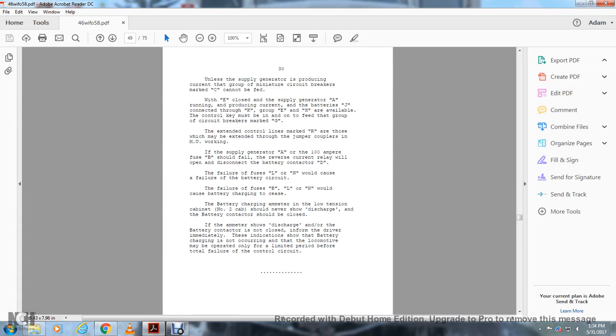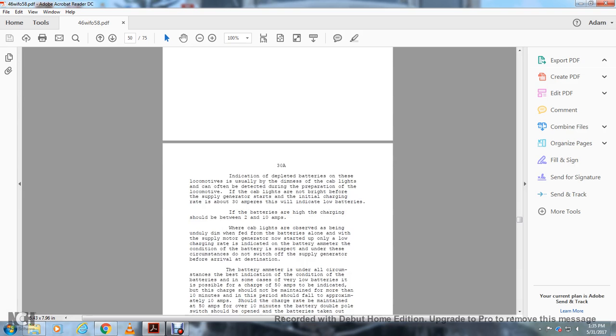If supply generator A or the 100 ampere fuse B should fail, the reverse current relay will open and disconnect the battery contactor D. Failure of fuses L or M would cause the failure of the battery circuit. The failure of fuses B, L or M would cause the battery charging to cease. The battery charging ammeter is in low tension cabinet number 2, which should never show discharge, and the battery contactor should be closed. If the ammeter shows discharge and/or the battery contactor is not closed, inform the driver immediately. The indications show the battery charge is not occurring. The locomotive may be operated only for a limited period before the total failure of the control circuits.